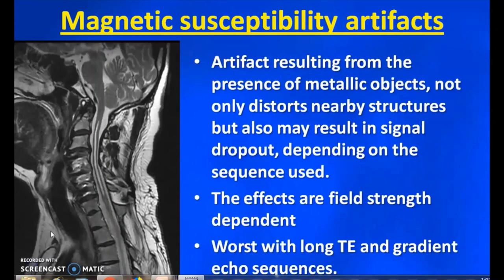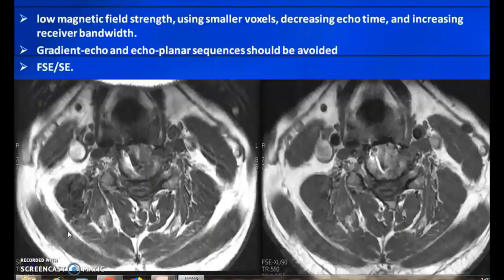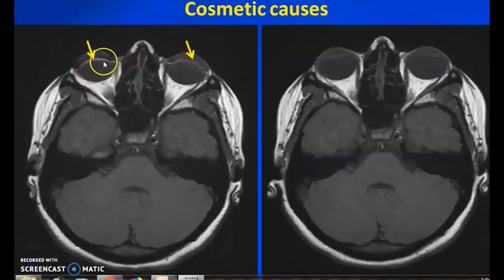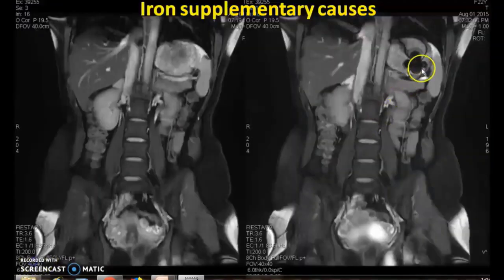Another common artifact is the magnetic susceptibility artifact, resulting from the presence of metallic objects causing signal distortion in nearby structures as well as signal dropouts. Depending on the sequence used — long TE and gradient sequences worsen this. The remedy includes using a lower magnetic field strength such as 0.35T or 0.2T, increasing matrix size, decreasing echo time, and increasing receiver bandwidth. Sometimes mascara or eyeliner causes this type of artifact — demonstrated by susceptibility artifact seen with eyeliner, and after its removal the artifact disappears. Iron supplements also create this type of susceptibility artifact.